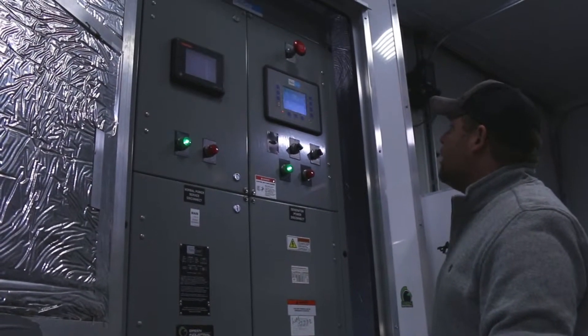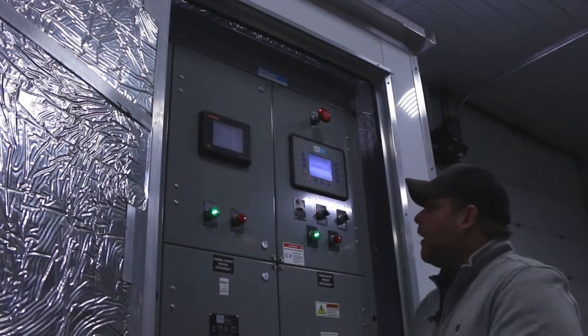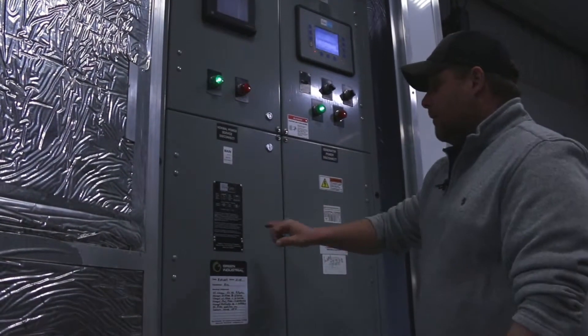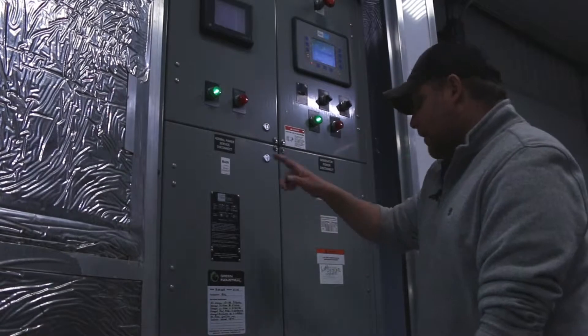To date this machine only has about 30 hours on it — just under or just over 30 hours. It's hardly broken in for a diesel engine. The bus itself inside the gear is 1200 amp, 208 volt rated all the way around.